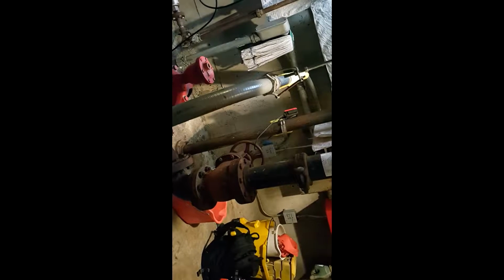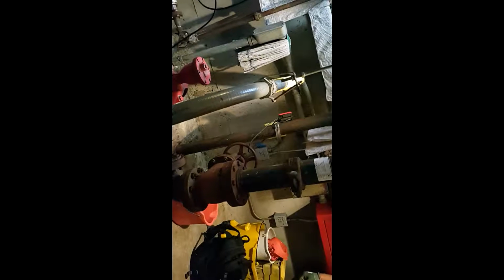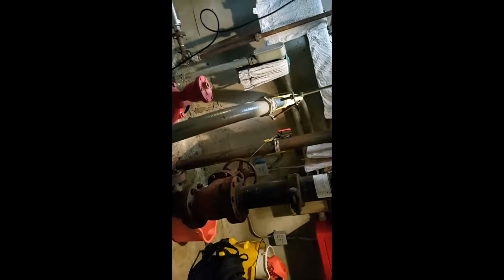You guys do the ventilation PMs here or no? No PMs here? Yeah. You guys need to get a PM program going. So it needs to be twice a year? Yeah, twice a year. And all you're doing is just checking lubrication. You just put one squirt, whatever the PM on your motor calls for. Exact same thing.